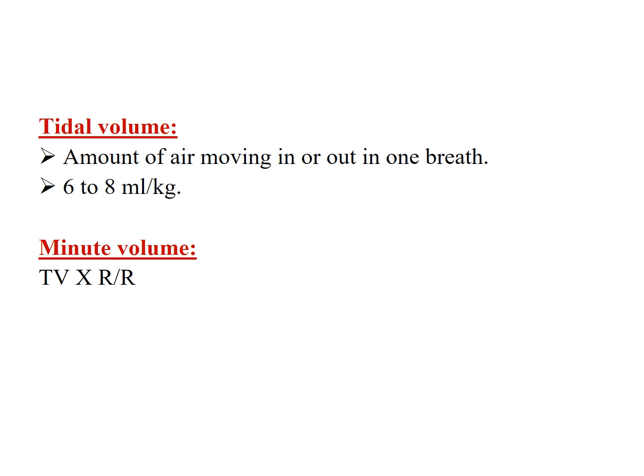So on the ventilator, there is a little display that will give you the tidal volume being delivered to the patient. Remember that there are two types of tidal volumes which are shown on your machine: the inspiratory tidal volume and the expiratory tidal volume. For all practical purposes, it is the expiratory tidal volume which is more important and more reflective of what has actually been reaching the alveoli. So keep an eye on the expiratory tidal volume, which you should actually. And the minute volume is the amount of air which goes in or comes out in 1 minute. So the tidal volume times the respiratory rate would give you the minute volume.